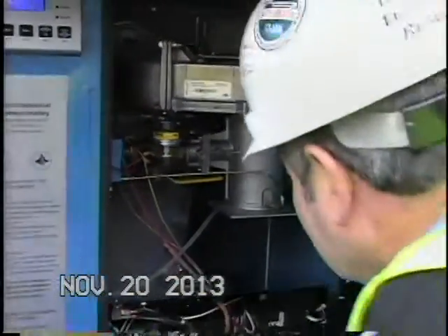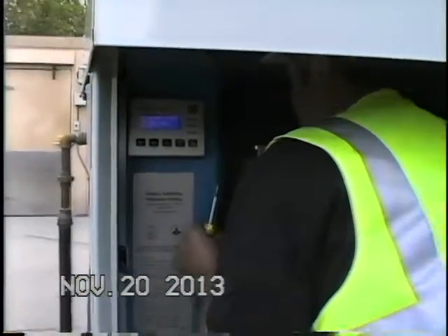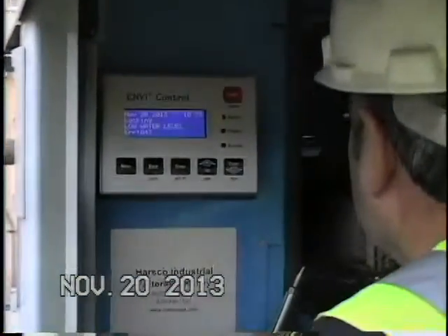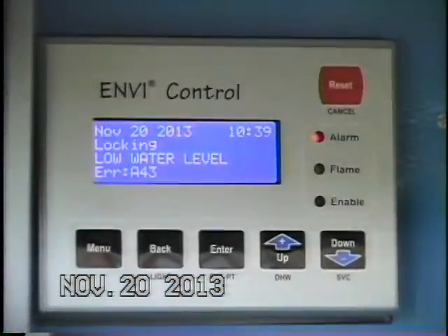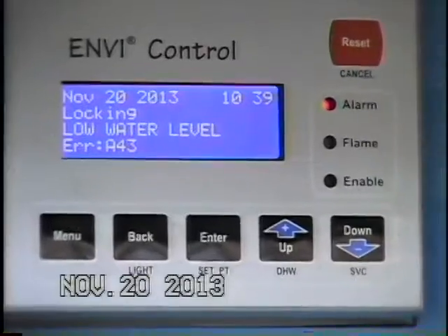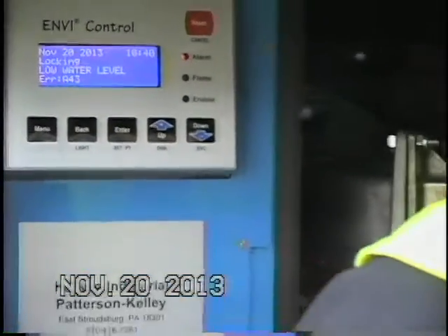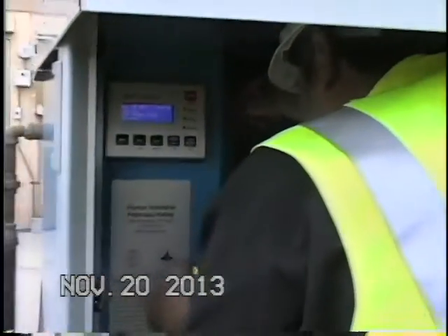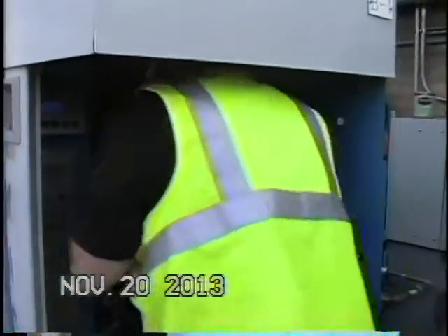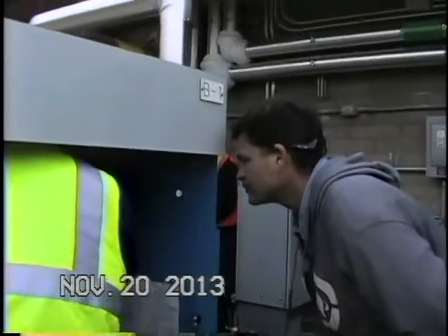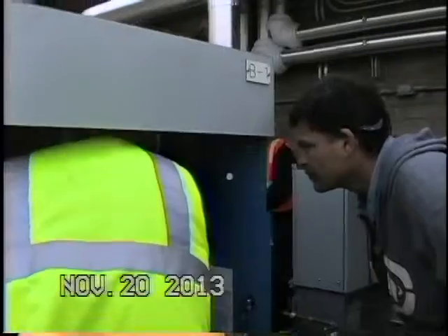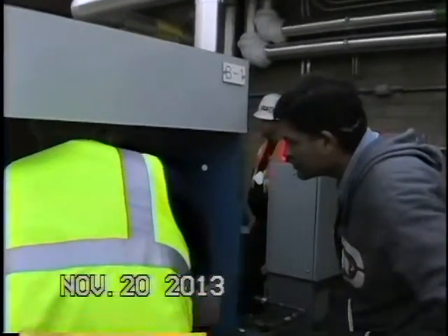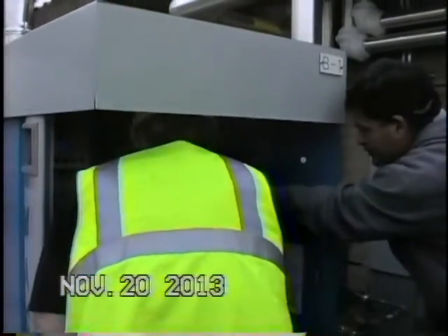You have to pull the top off to get to it. And then that's gas pressure switch right there? Yeah, this is an air switch. Oh, okay. Here, this is an air switch. Where's that gas pressure switch? I don't know if you can see them. It's right here. It's just a little manual one on the gas valve itself, but it must be an auto reset. So this is a different type. This one doesn't have it. So this is air, that's gas? Yeah, this is the gas.